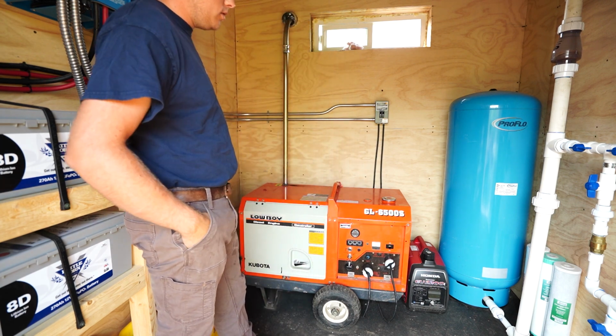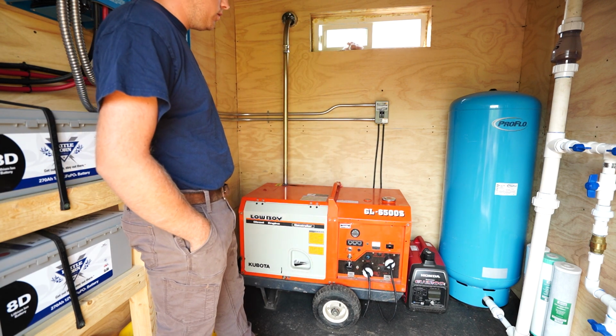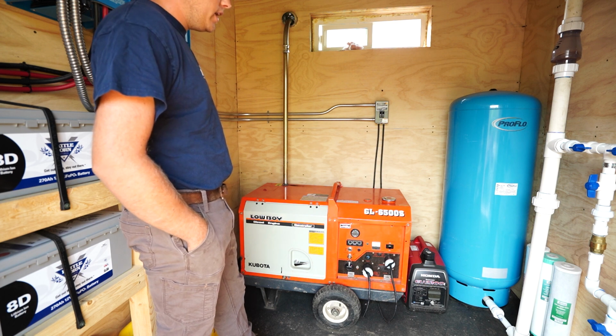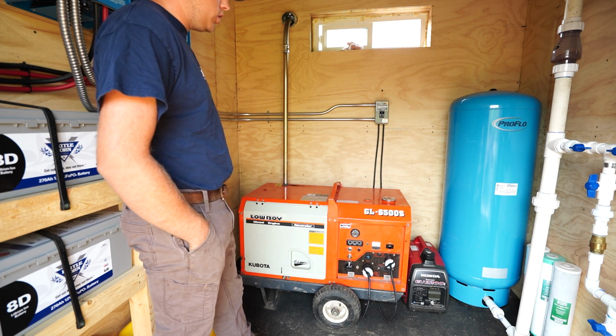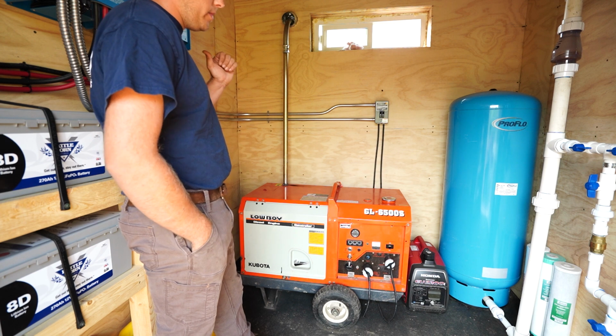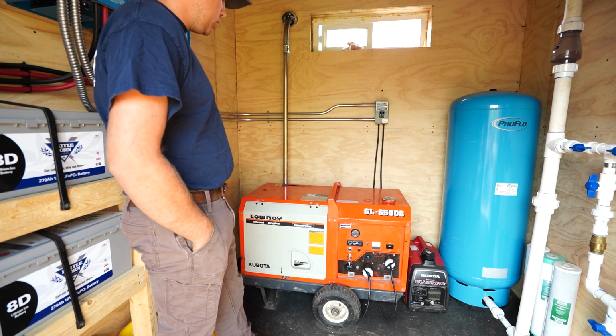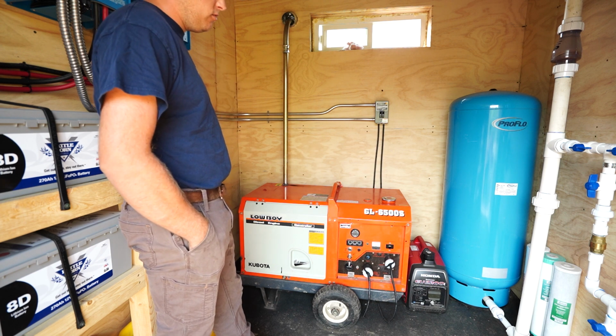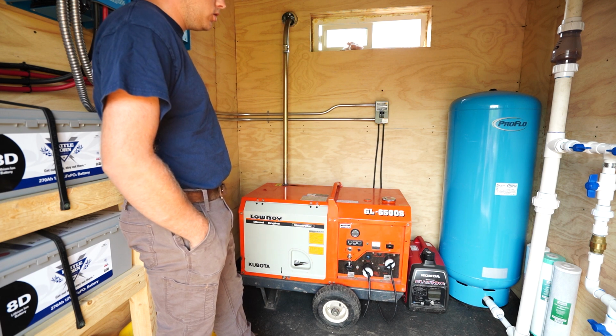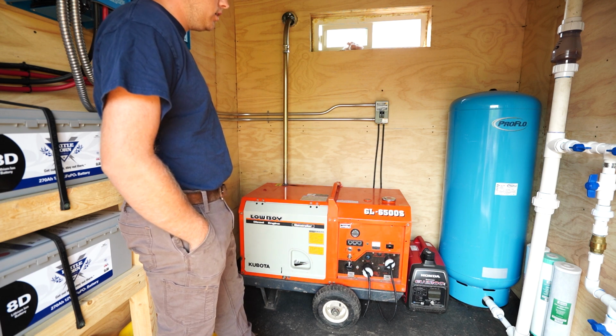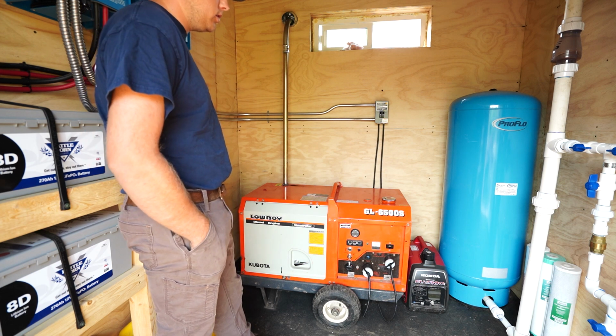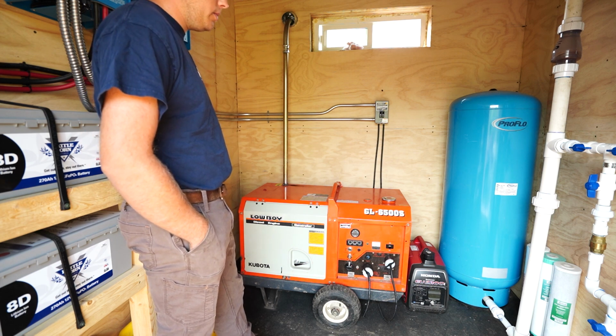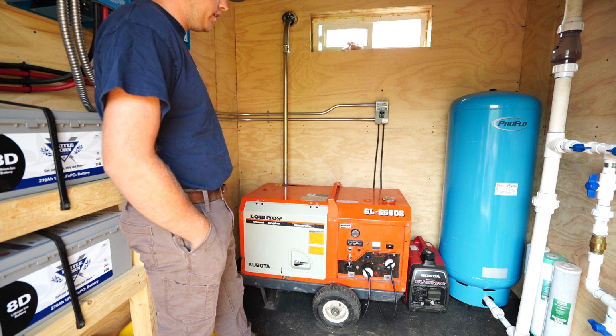We have our generator, a diesel generator, 240 volt, tied into our inverter chargers, which then charge our batteries. It's just a Kubota generator. We can get about 7 or 8 hours on a tank of fuel, but it takes about 4 hours to charge our batteries from about 20%, so we get about 2 charges out of a tank of fuel.